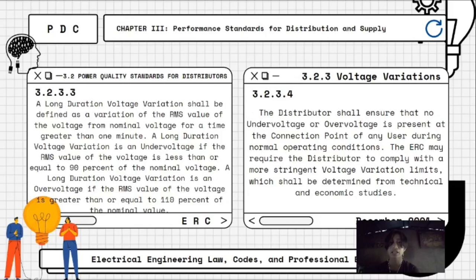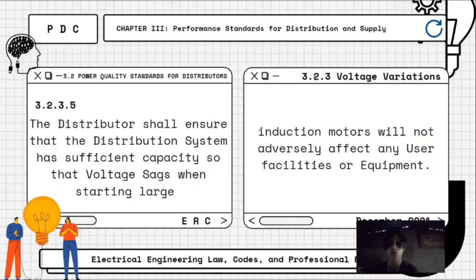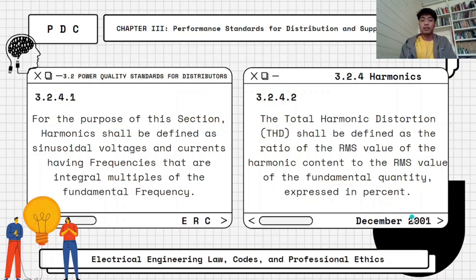The distributor shall ensure that no under-voltage or over-voltage is present at the connection point of any user during normal operating conditions. The ERC may require the distributor to comply with more stringent voltage variation limits, which shall be determined from technical and economic studies. The distributor shall also ensure that the distribution system has sufficient capacity so that voltage sags when starting large induction motors will not adversely affect any user, facilities, or equipment.